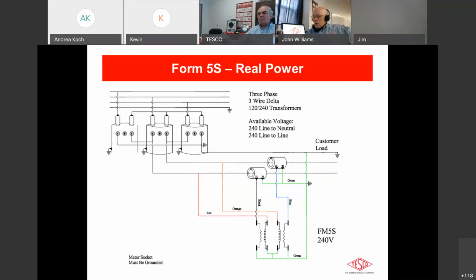And if somebody said they wanted their board to work with 5S meters, that became a bit of trouble for us, where we would have to make sure that we didn't apply a CT across where a voltage coil would be. Obviously, you end up with a short circuit and then blown fuses or circuit breakers, and it tended to make a mess of the test board circuitry. Like I said, nowadays we've got computers and software, and we handle that a lot easier. But in the old days when we were doing this with relay connections and so forth, it became a bit of a challenge, as we say.